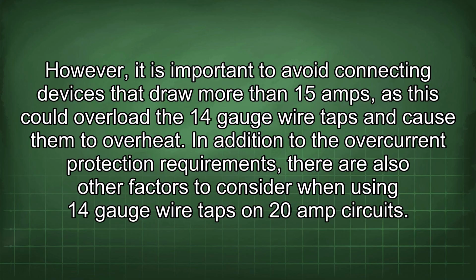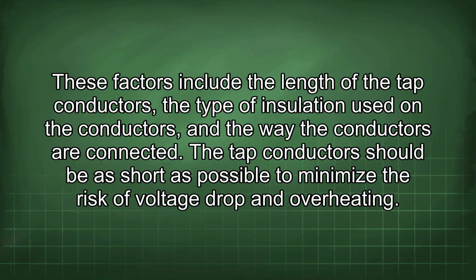In addition to the overcurrent protection requirements, there are also other factors to consider when using 14-gauge wire taps on 20-amp circuits. These factors include the length of the tap conductors, the type of insulation used on the conductors, and the way the conductors are connected.